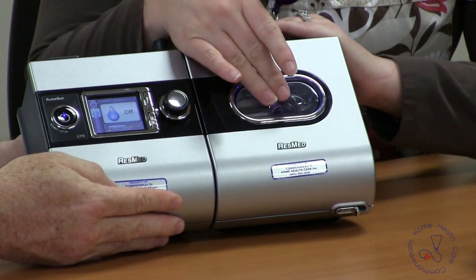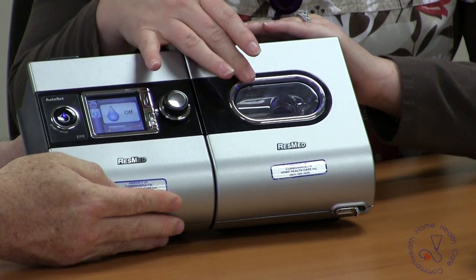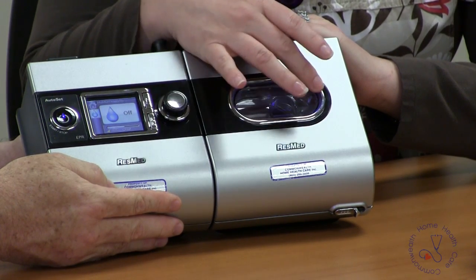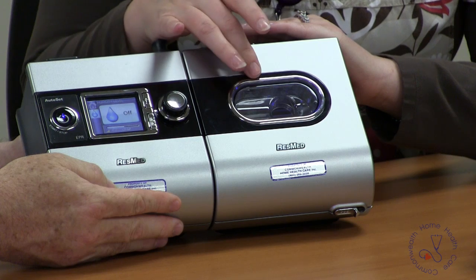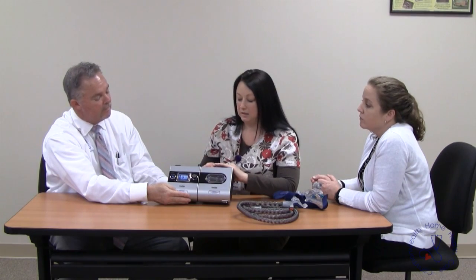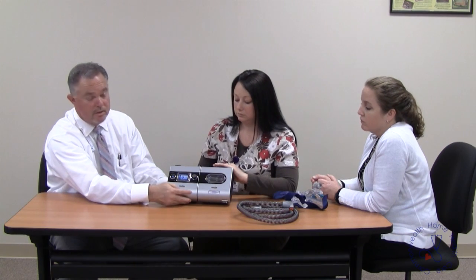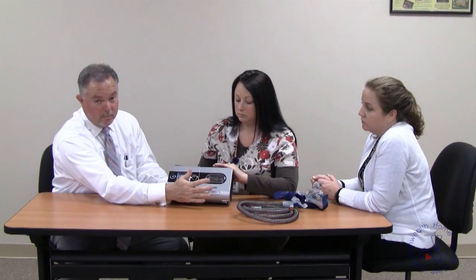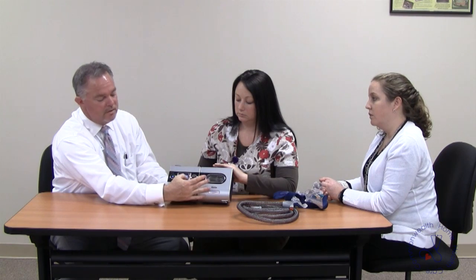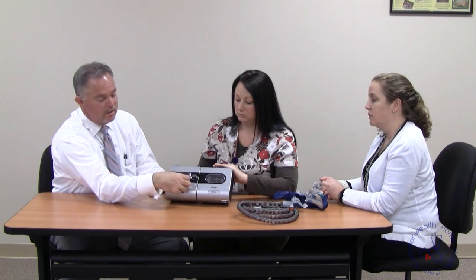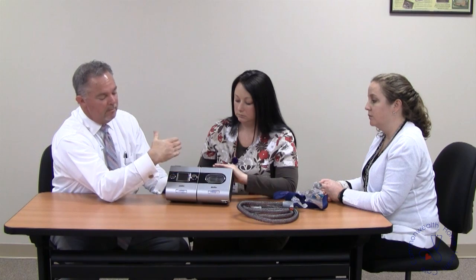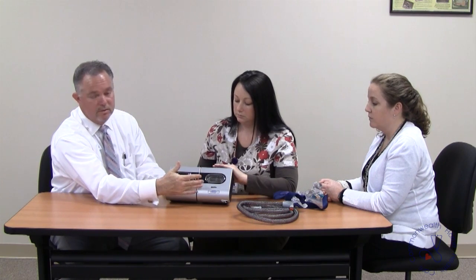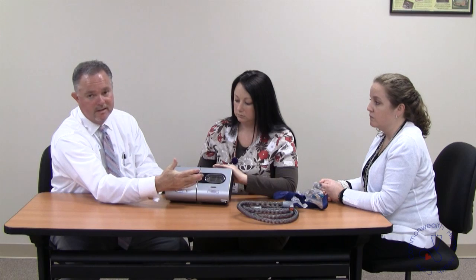There's a light on this side. When the heater is not used, this light's going to be blue. When the heat is used, the light will be orange. That doesn't mean anything wrong. It just means that this is heating. Yeah, I think that's a really important feature. A lot of times we're used to red lights or orange lights meaning a problem. In this case, it's a good thing. It's saying that your heat is on, just reminding you that you're using the heated humidifier when you use it. Because not all patients will use heat. They will just use the humidity in itself.